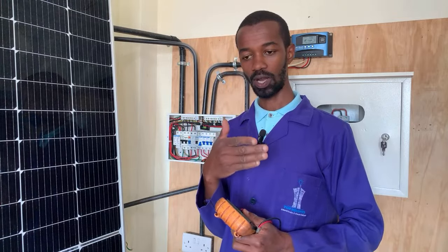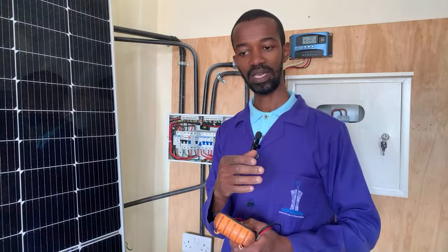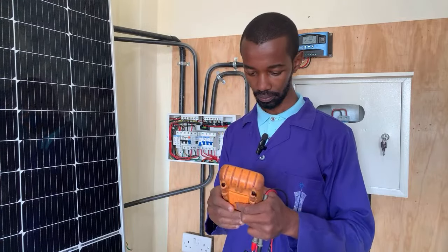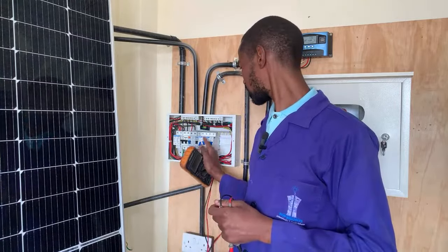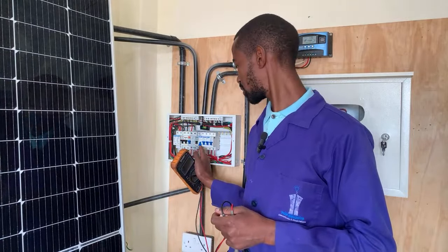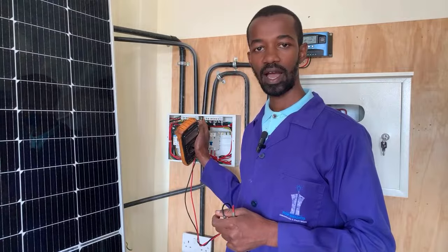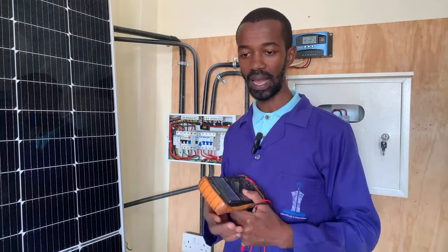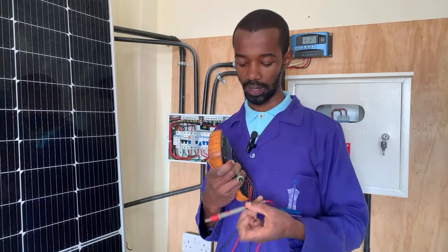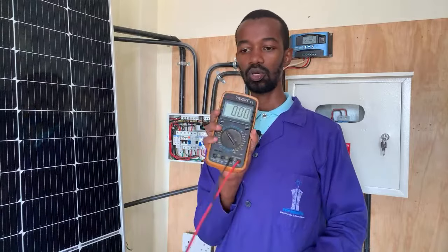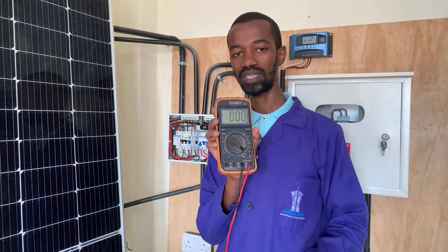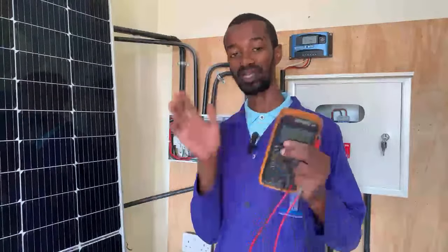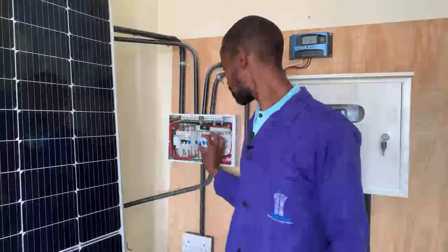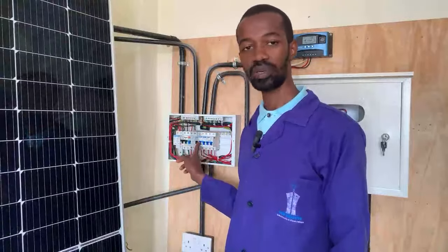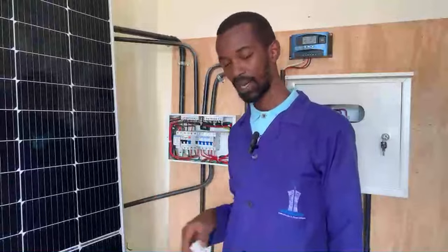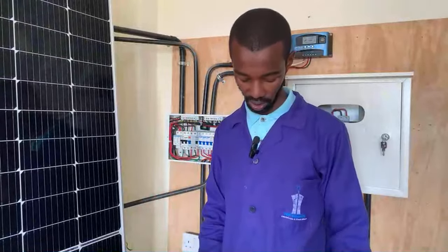It could be the electric cooker circuit, the pump circuit, or the instant shower head circuit, depending on which circuit is having a problem. Once you place the probe at the output of the MCB that has tripped and at the neutral, or the earth connection, and there is a problem, there will be a beep. In most cases, there will be that beep. Otherwise, you are not supposed to get a beep or a 00. You're supposed to get a 1, meaning an open circuit. There is no short circuit. That is when you will put on that circuit breaker, the miniature circuit breaker, and that will mean that circuit is okay.